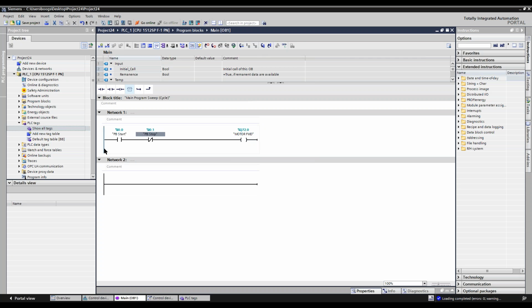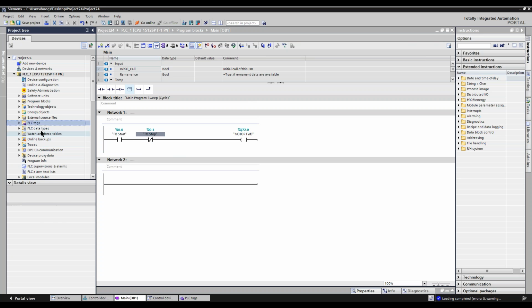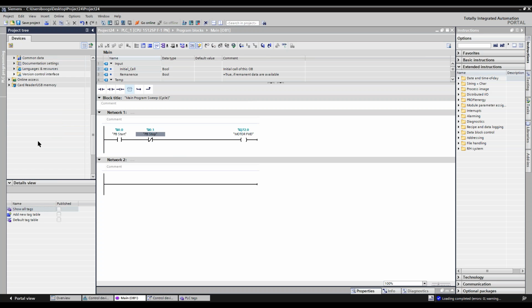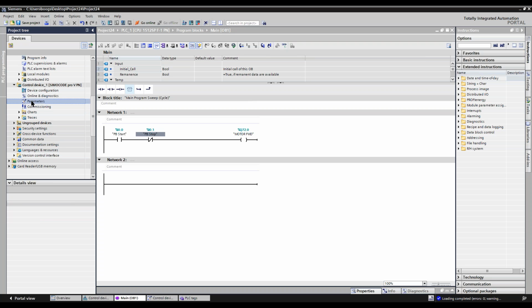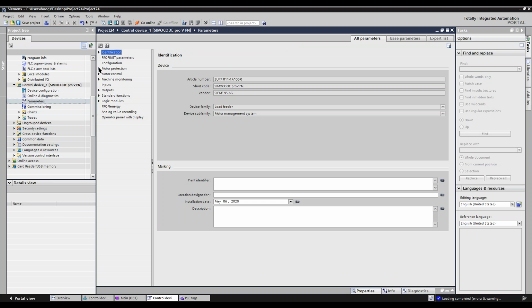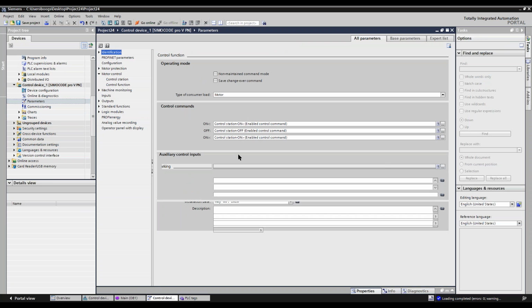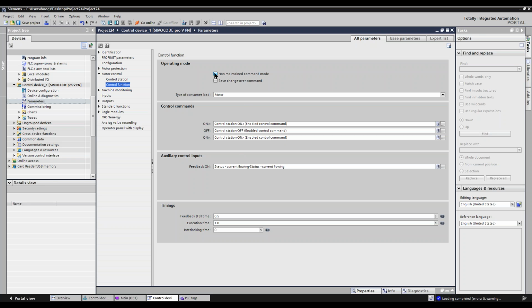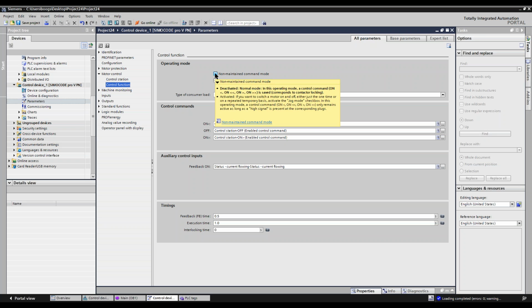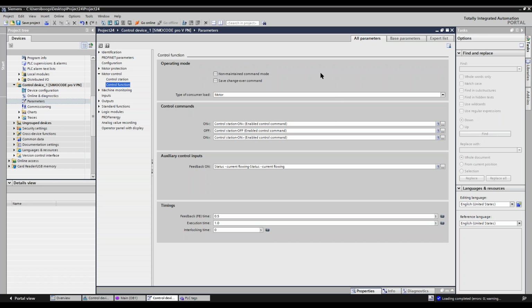Now notice I don't have that interlock that I thought I needed. I don't need that interlock anymore, because if I go over here to the SIMOCODE parameters, and I go to motor control and control function, right here, all I do is non-maintained command mode, meaning if I check this box, I have to hold the button down to keep the motor running in local. Or if I uncheck it, then I just push the button and it continues to run. Okay? All right, we're rolling up on time.